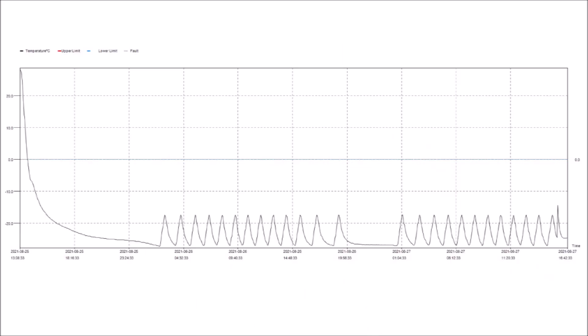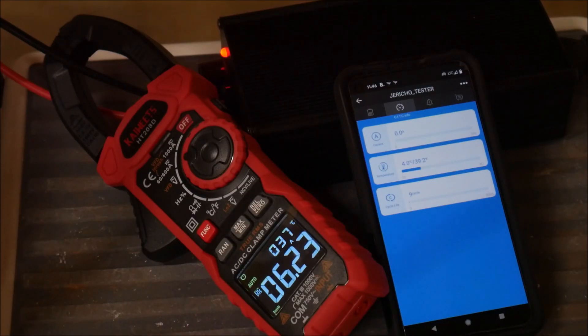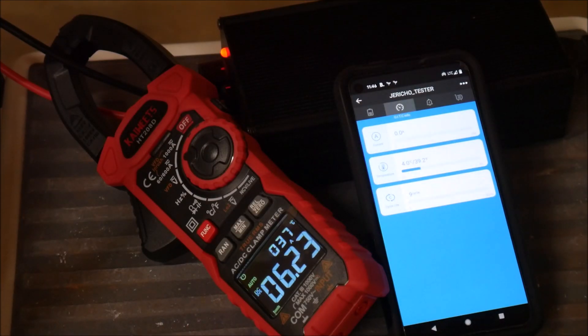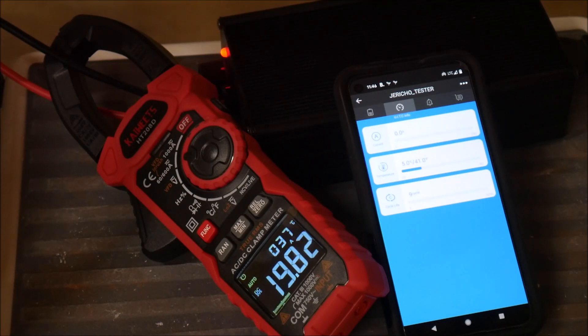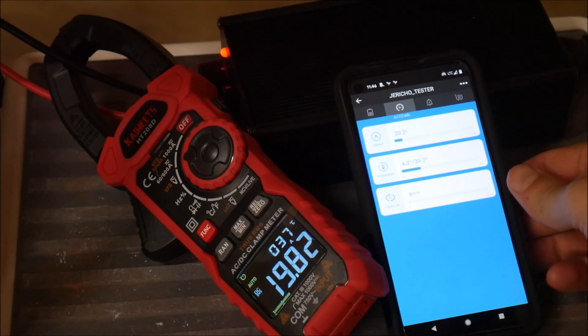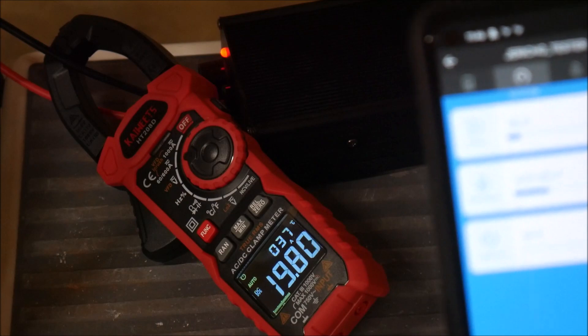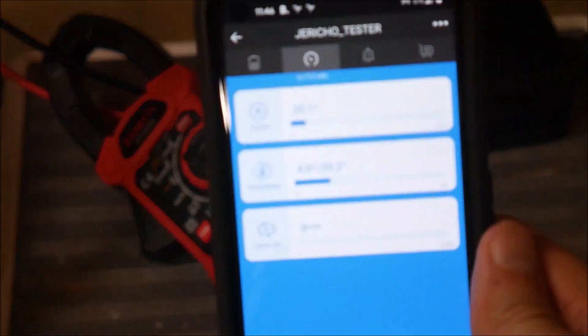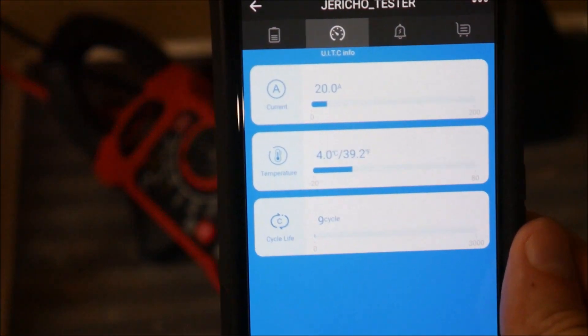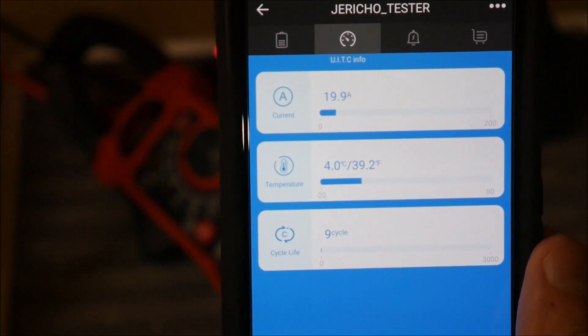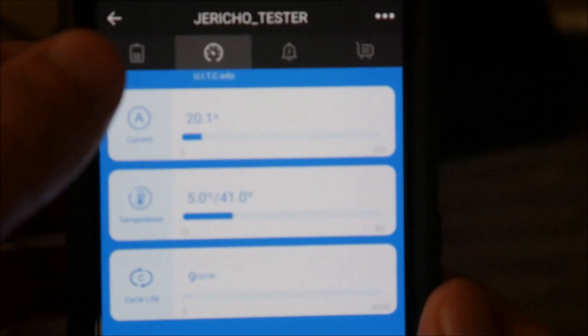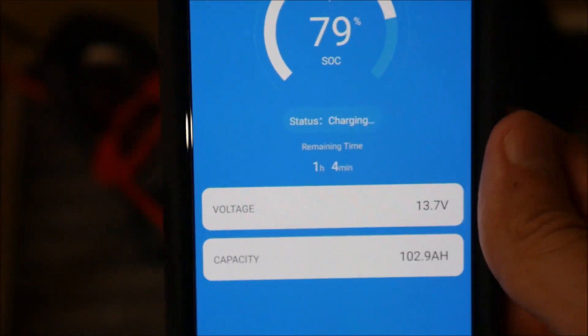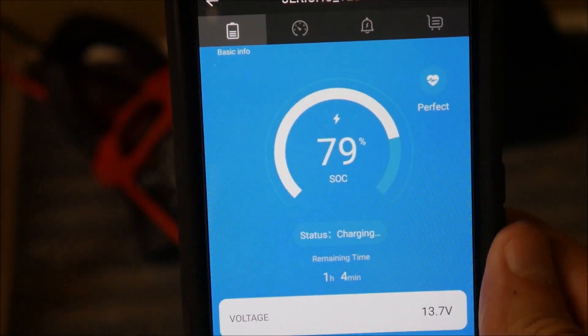Here you can see the data from the temperature logger. The freezer was well below zero for over two days and we can say 100% without a doubt that the internal temperature of the battery was well below the cold charging protection threshold. And we were able to watch the battery warm itself up slowly to a healthy margin above freezing, and then the heater turned off and the charger was able to start charging. So we passed both tests here. The internal heater works as it is supposed to, and the cold charging protection of the BMS works great as well.